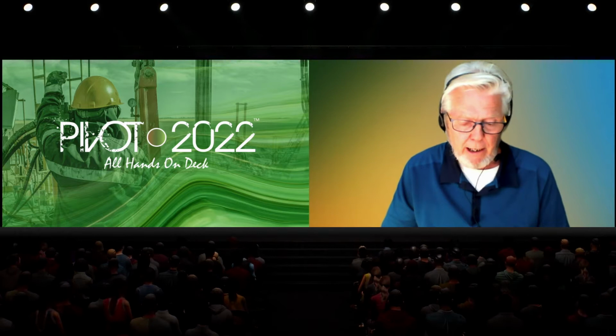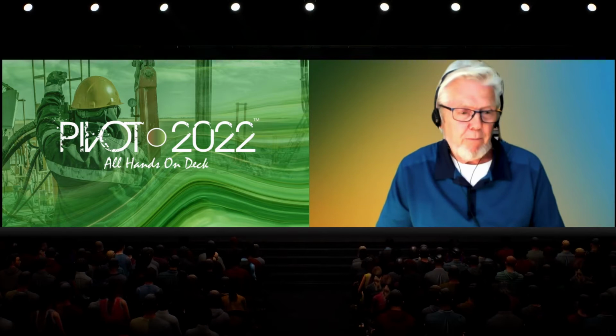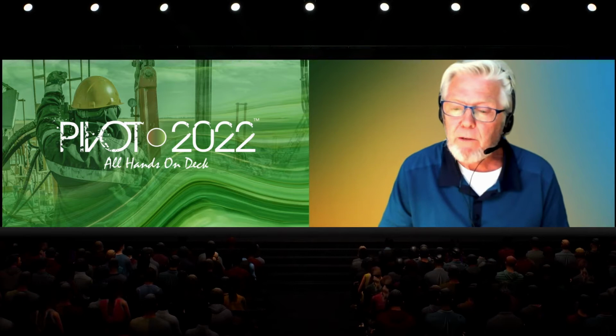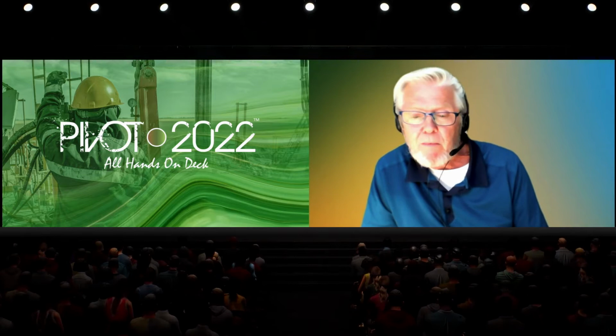Under these circumstances, normally people just cement the well and forget it, but the IDDP program decided to flow test the well, and we succeeded very nicely and created the world's first magma-driven EGS system in 2010 to 2012 during the testing. We managed to deal with hostile fluid chemistry, and we were just about to scale up the pilot plant when a 2-inch surface valve broke, which led to a series of problems. So in the end, we had to control the IDDP well with cold water, which completely ruined the production casing.